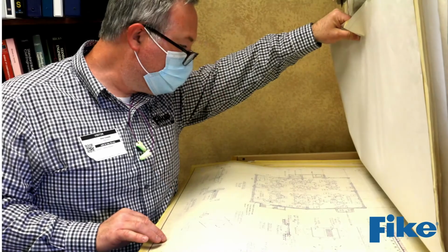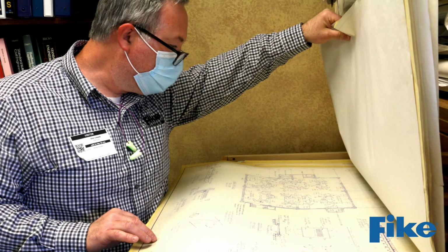The next step in preparing for DHA is to gather all relevant process documentation. So this will be process flow diagrams, this will be facility layout diagrams, this will include equipment sheets from the original equipment manufacturers, also explosion protection documentation. So if you have existing explosion protection equipment, you'll want to see the design documentation for that.